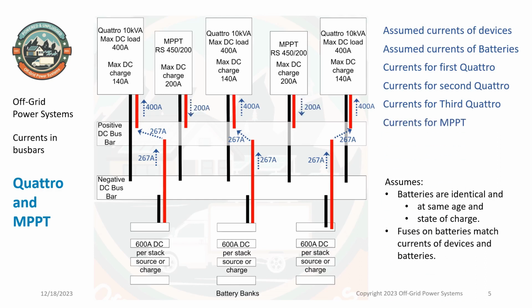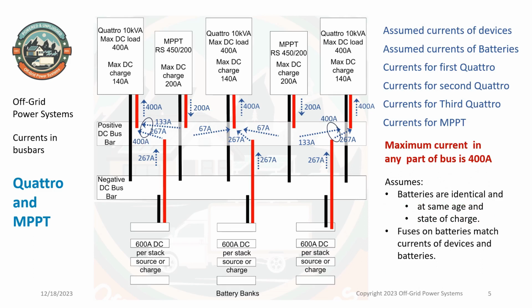Here come the MPPTs to save the day. Each supplies 200 amps, which provides the remaining current. The maximum current in the two places in the bus bar combined to 400 amps. The middle part of the bus bar is less than 400 amps, although the currents combine at each connection point to 400 amps.